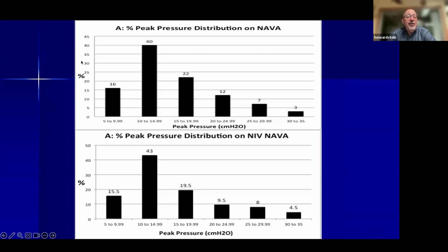These graphs show the percent of breaths on the vertical axis, and on the horizontal axis are the breaths divided into pressures, 5 to 10, 10 to 15, 15 to 20, 20 to 25, all the way up to 30 to 35. And all these babies had their peak pressure limits set at 40. And as you can see, our typical thing would be setting a peak pressure of 20 when we do conventional ventilation. We typically start at around 20 over PEEP. And you can see 70% of the breaths are actually much lower than 20, of which over 50% of the breaths are lower than 15.